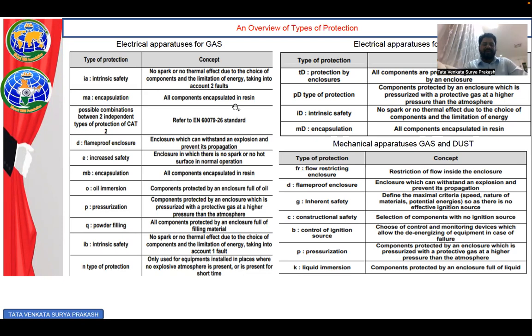Similarly, with encapsulation, for example, all components are encapsulated in resin, or with powder filling, all components are protected by an enclosure full of filling material. We use the filling material so that it cannot create an explosive atmosphere. For dust, there is also a type of protection where components are protected by an enclosure pressurized with a protective gas at a higher pressure than the atmosphere, so that we can avoid a dust explosion environment forming and subsequently leading to an explosion.